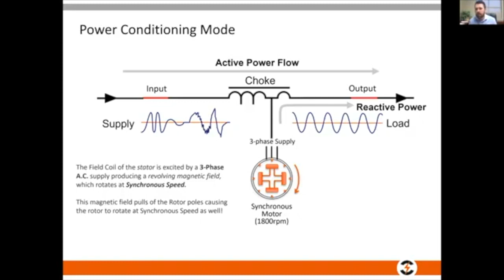The challenge is what happens when the input at the utility fails. Let's say that input breaker on the upstream side here opens. Well, it's as good as pulling the plug, because when I've lost my power, my synchronous motor will slow down. It's no longer got a source of energy. And if this slows down and the input breaker's open, this waveform is going to be all over the place until a point where you just lose power. So this is fantastic for power quality, but I need something else to turn it into a UPS.